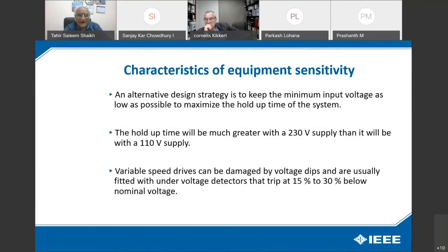An alternative design strategy is to keep the minimum input voltage as low as possible to maximize the hold-up time of the system. The hold-up time will be much greater with a 230 volt supply than it will be with a 110 volt supply. Variable speed drives can be damaged by voltage dips and are usually fitted with undervoltage detectors that trip at 15 to 30% below nominal voltage.